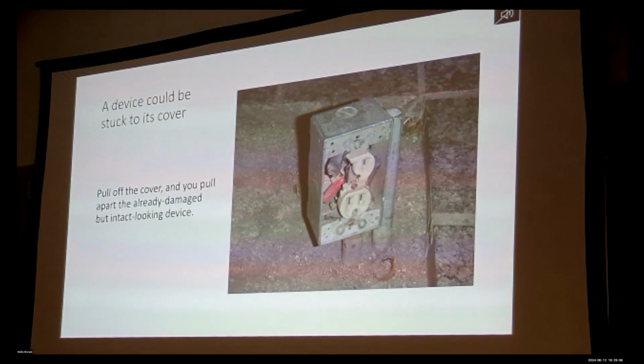It's also a place that flippers are least likely to rewire, but they're likely to put a new fixture on, which is not rated, which requires a 90 degree C wiring minimum, right?